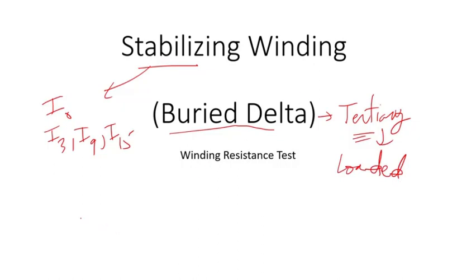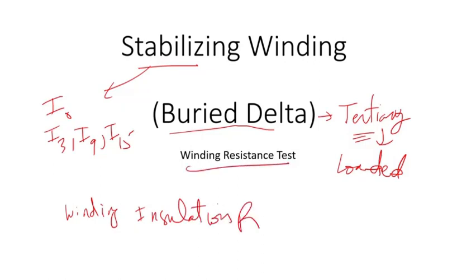So previously I spoke about winding insulation resistance. Now I'm going to talk about winding resistance. These are two tests you can perform on the stabilizing winding. So this delta, basically you have 3 coils that are wound separately. Then what they would do, they would connect these 2 terminals here. So basically, you have start and finish of each coil. Then you would connect 2 terminals, then the 2 corners of the delta. The third one you would not connect.